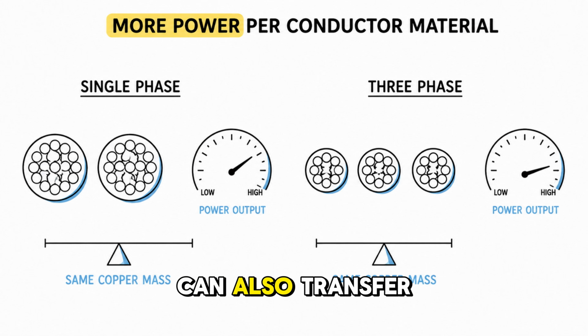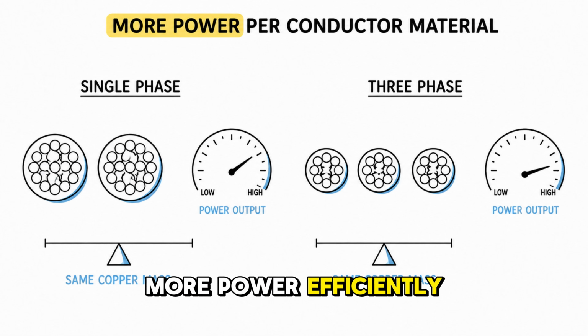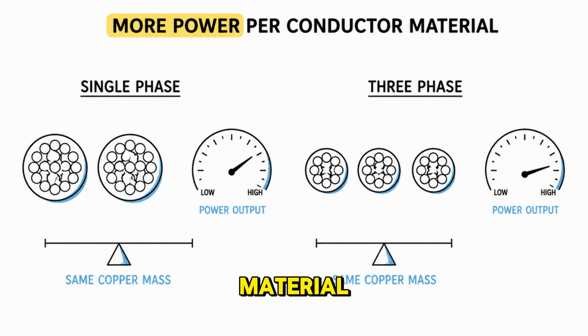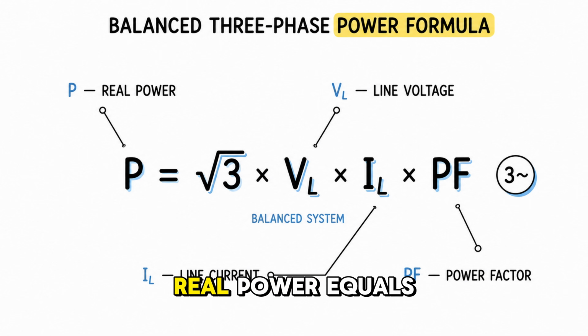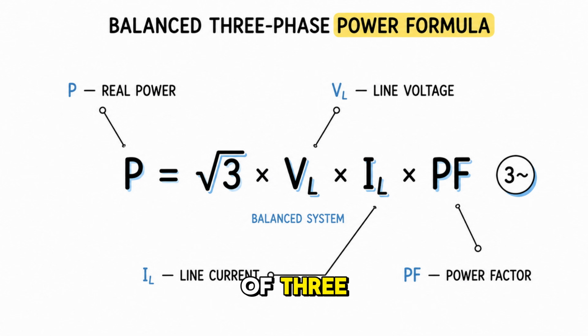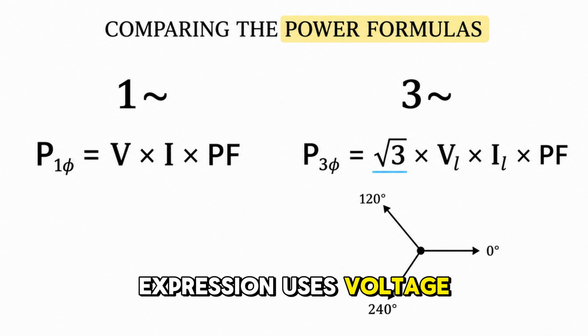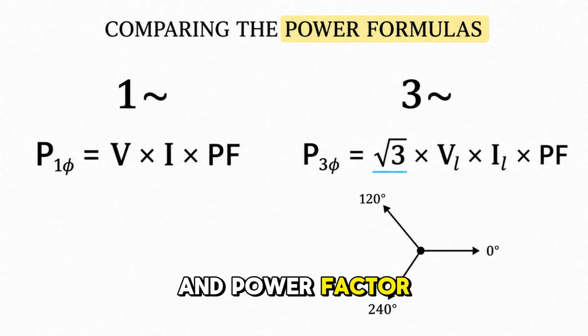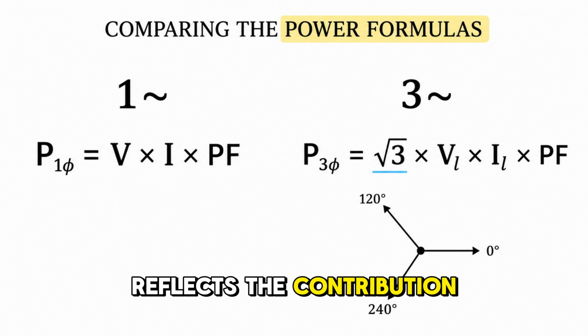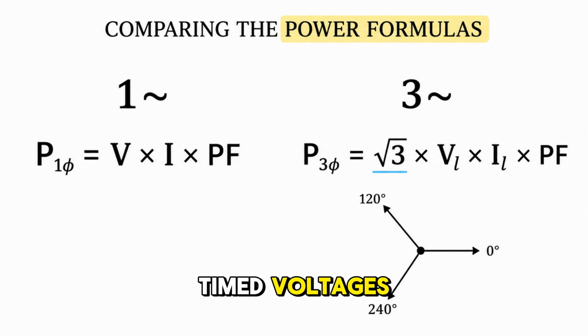Three-phase distribution can also transfer more power efficiently for a given amount of conductor material. For a balanced system, real power equals the square root of 3 multiplied by line voltage, line current, and power factor. The single-phase expression uses voltage multiplied by current and power factor. The formula reflects the contribution of all three timed voltages.